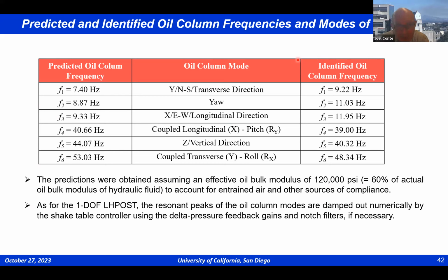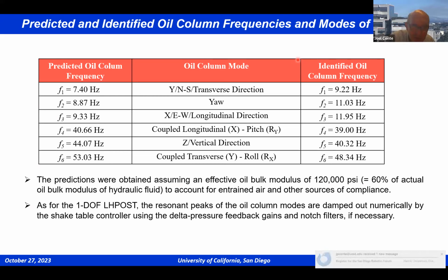Now imagine this rigid platen, a rigid box with 6 degrees of freedom in three-dimensional space, right? And each actuator, when the oil is pressurized, represents a spring. The oil column in each actuator, horizontal and vertical, is like a spring. So if you do a 6 degree of freedom eigenvalue analysis, you would get the predicted oil column frequencies that are here, as long as we take an effective oil bulk modulus of 60% of the actual oil bulk modulus of the hydraulic fluid to account for entrained air and other sources of compliance. This is knowledge we have by experience, right? And then these are the identified oil column frequencies.